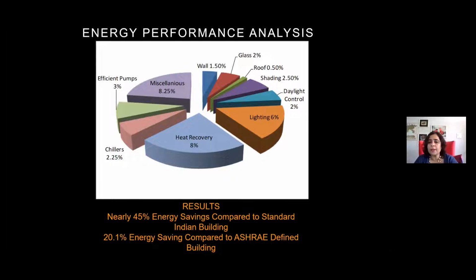These passive measures helped us save about 7 to 8% of energy, and the remaining savings came from efficient pumps, efficient chillers, and heat recovery wheels, which pre-cool the fresh air coming in. We also run the air conditioning without chillers during fair weather seasons, November, February, and March, when a regular building would still need air conditioning due to heat from people and equipment, but here we just pump in fresh air without using chillers.